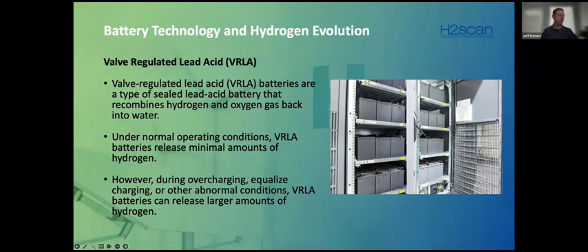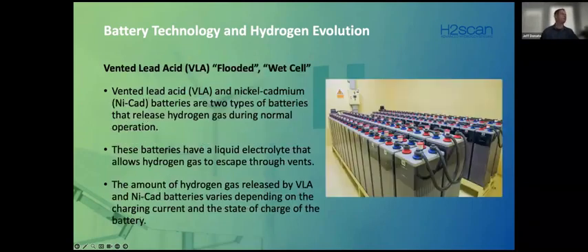Some call it boost charging. But it can also happen under any abnormal conditions where you have excessive heat, where you're not doing temperature compensation, or where the charge voltage may be too high for the temperature. So these batteries do have the potential to gas hydrogen. Just because they are recombinant, or more of the sealed type, doesn't mean they're completely sealed. What we're used to seeing in substations, of course, are the vented lead acid batteries.